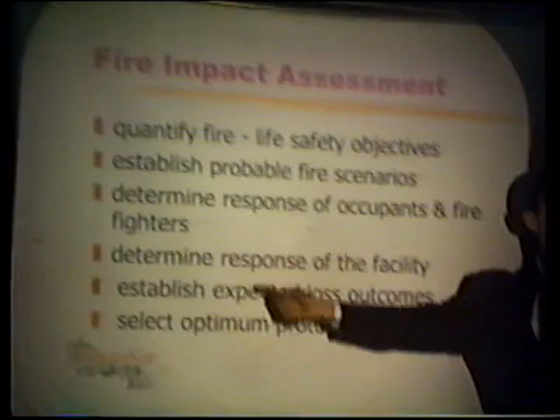Now, in order to do that, you're going to have to quantify your fire life safety objectives. You're actually going to come up with probable fire scenarios in a building. Then you're going to determine the response of the occupants and potentially how the firefighters might react. Determine the response of the physical facility. That is, if we have a fairly sophisticated system, when we say the facility, how does the rated construction react? How do the sprinklers react? Fire alarm? If we have smoke control, how does it all sequence together? But we have to determine what that response is.